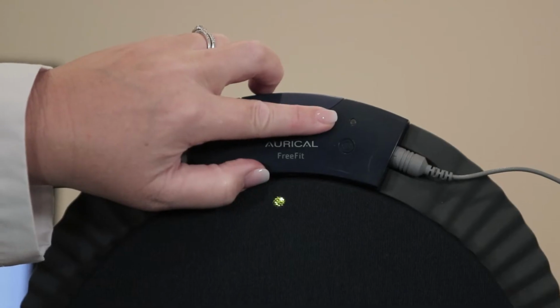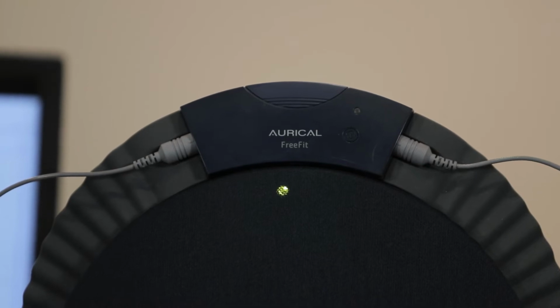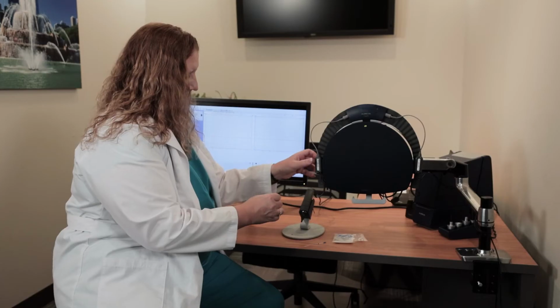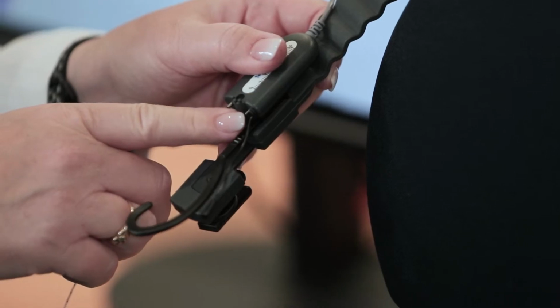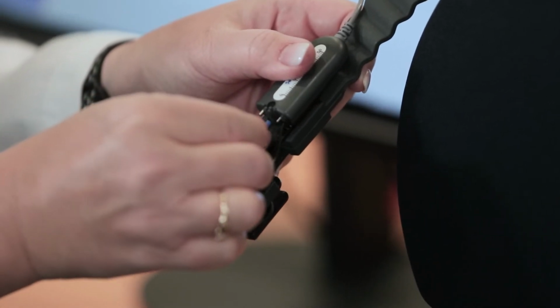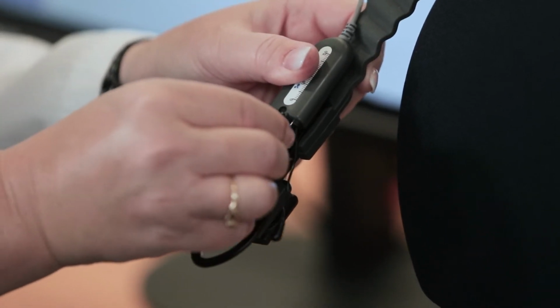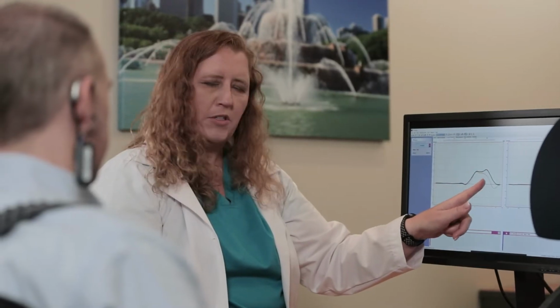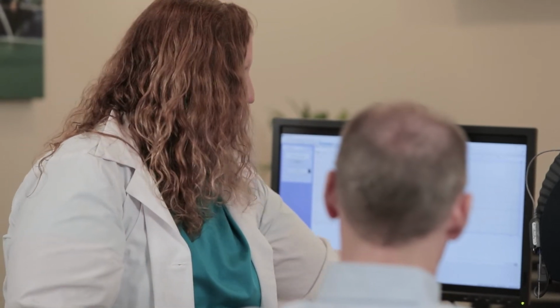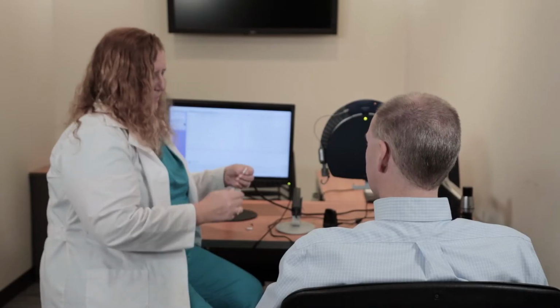Make sure the Aurical FreeFit collar is turned on for connection in OtoSuite. When setting up for verification, you must connect a new probe tube, or 2 new probe tubes if you are fitting binaurally, for every new session. It is recommended to perform probe tube calibration every time you connect a new probe tube. As demonstrated in the previous video, Getting Started, we have already connected and calibrated the probe tubes for this fitting session. The next step is measurement of the client's unaided responses.